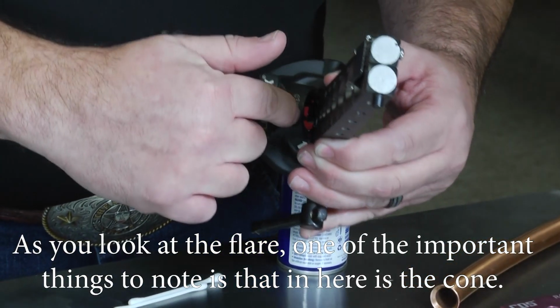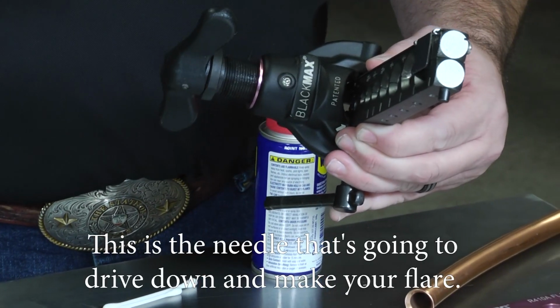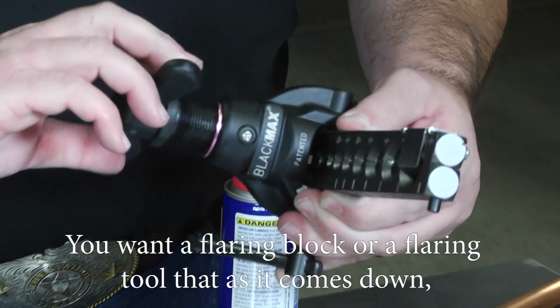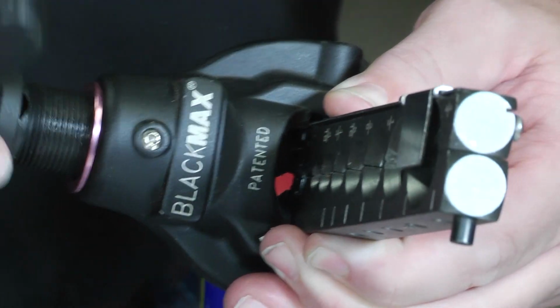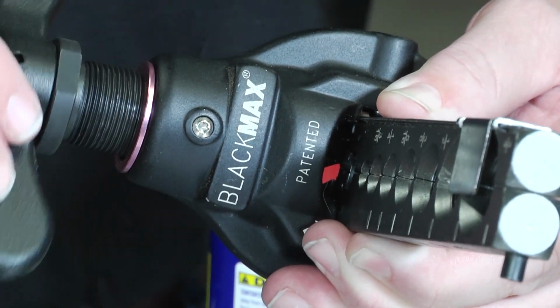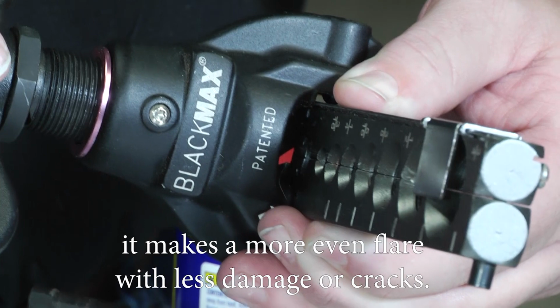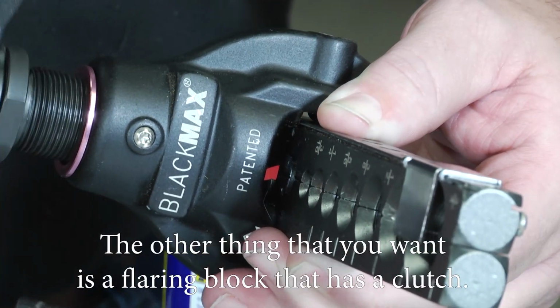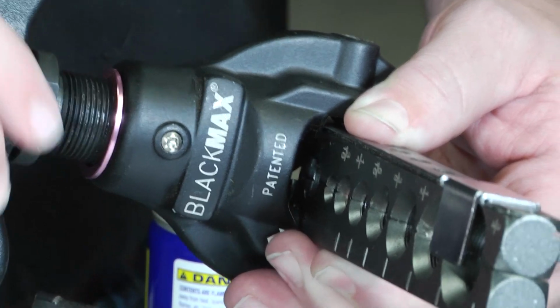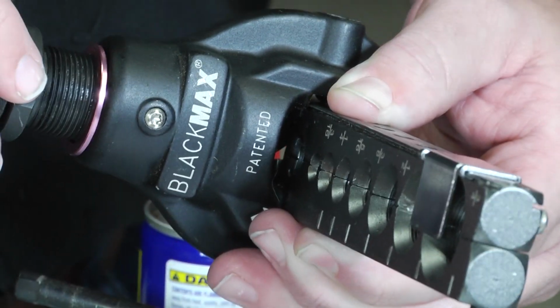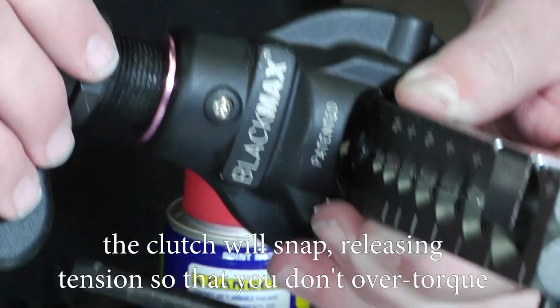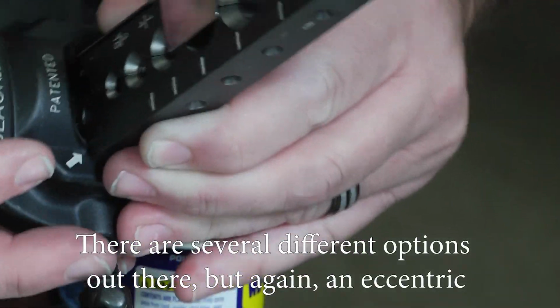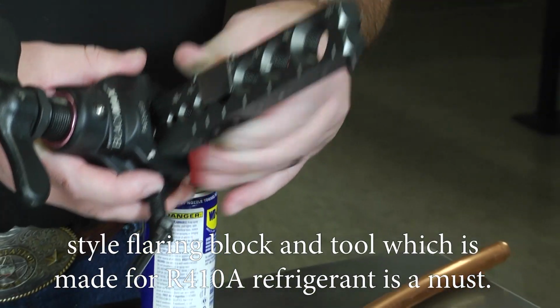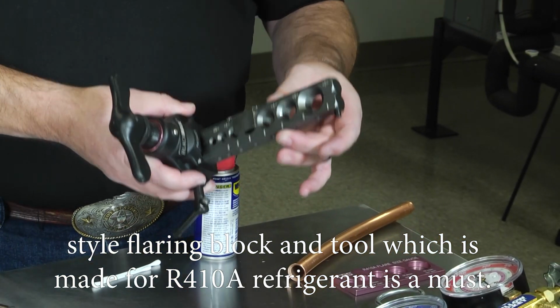Now, as you look at the flare, one of the important things to note is that in here is the cone. This is the needle that's going to drive down and make your flare. You want a flaring block or a flaring tool that as it comes down, that cone orbits in an eccentric pattern. It makes a more even flare with less damages or cracks. The other thing that you want is a flaring block that has a clutch. What the clutch does is as soon as the flare is completed, the clutch will snap, releasing tension so that you don't over-torque or overstress the copper in your flaring system. There's several different options out there, but again, an eccentric style flaring block and tool which is made for R410A refrigerant is a must.